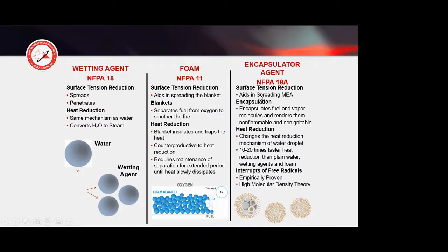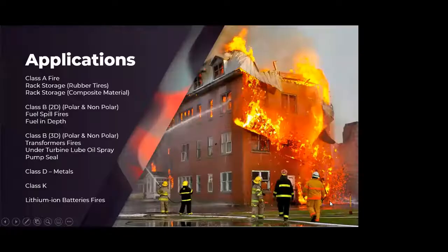Encapsulator agents reduce surface tension, similar to a foam, which aids in spreading the micelle, spherical micelles, the micelle encapsulator agent. We're encapsulating fuel and vapors inside the spherical micelle, separating the fuel from the oxygen on a chemical molecular level. We change the heat reduction mechanism of the droplet to account for 10 to 20 times faster heat reduction and interrupting the free radicals. So here you're working on 2 legs of the fire tetrahedron. Here you're working on 4 legs of the fire tetrahedron at the same time.